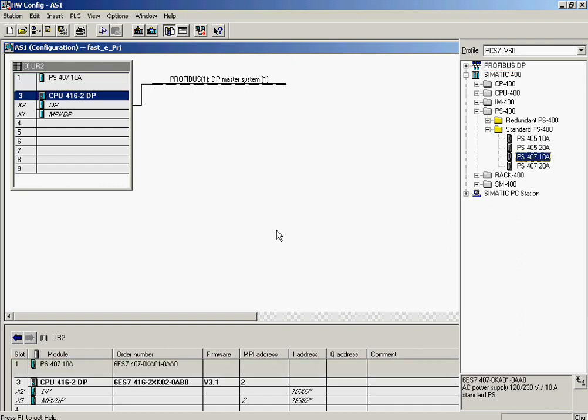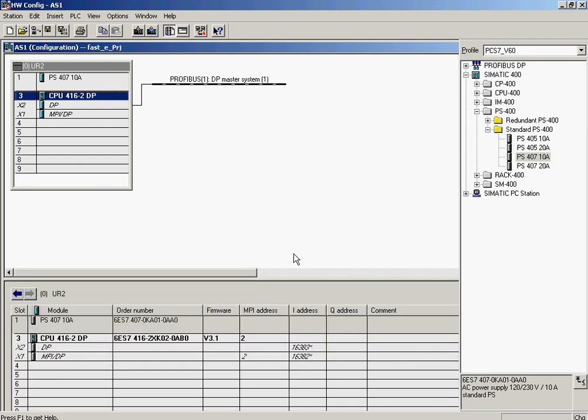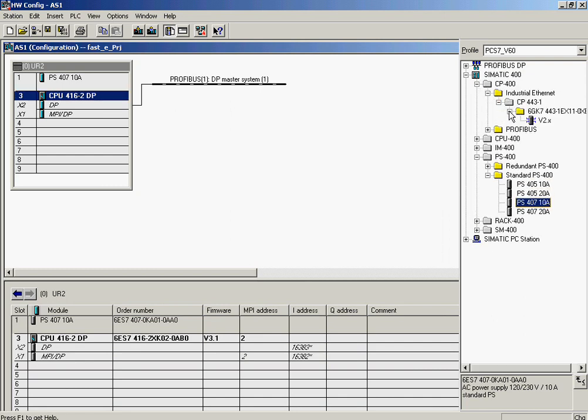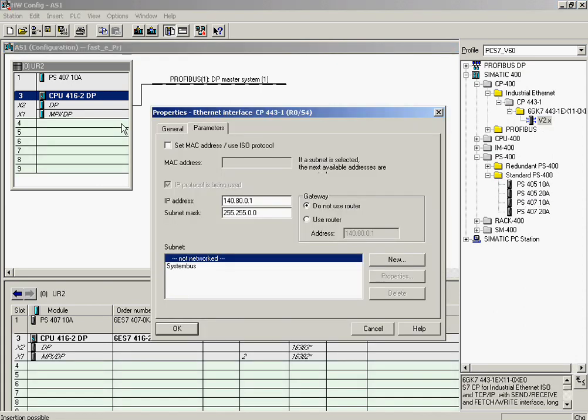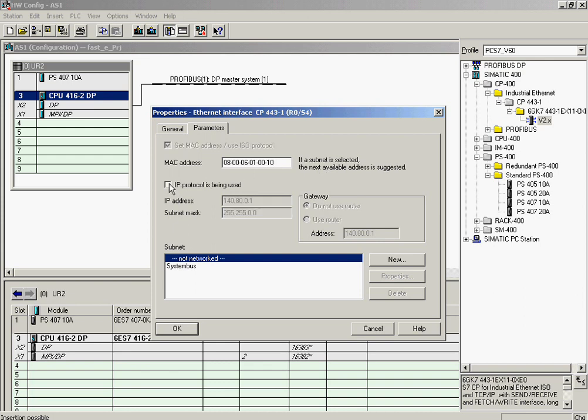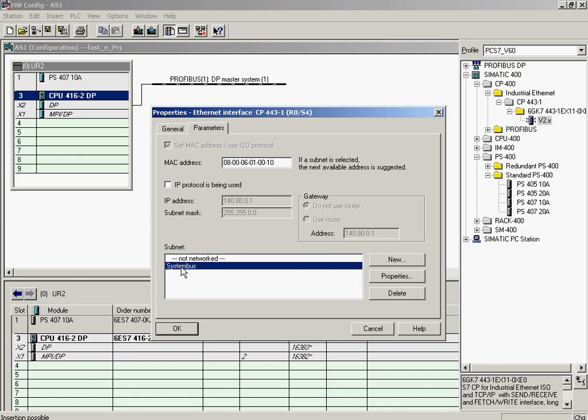The configured CPU matches the actual component. Next, the communications processor CP443-1 is inserted for Ethernet communication. Now various settings are defined in the properties dialog. First, the ISO protocol is activated and the MAC address is entered. The IP protocol is not used, so it is deactivated. Finally, the communications processor is assigned to the system bus network.